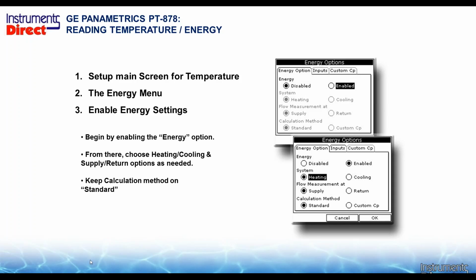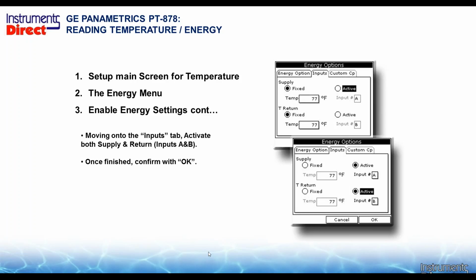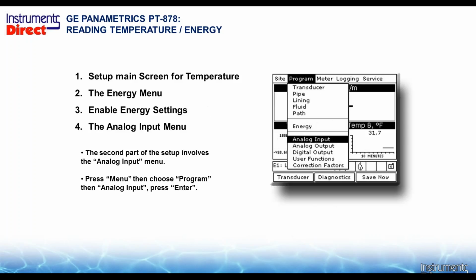We begin by enabling the energy options. From here we choose heating and cooling and supply and return. So now you're identifying that one temperature sensor is for the supply and one temperature sensor is for the return. So when you get your data, everything is boxed up accordingly, and you can go backwards and find out what's going on. Keep your calculation methods on standard. Then we need to move into the input tabs. We need to activate both the supply and return on the input. This is the data you're putting in. Once we've confirmed this, we hit OK.